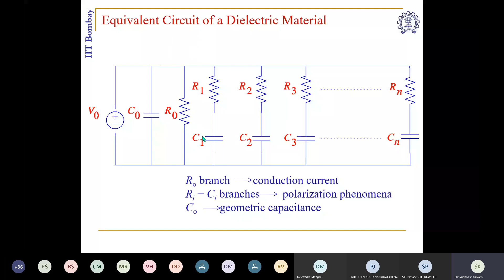Whereas this R0 is the final element. When we apply the DC voltage, eventually all the capacitances you see in this circuit will get charged, and then all those will become open circuited from the electric circuit point of view. The only element that will remain in this circuit will be R0. So V0 upon R0 is the final steady state leakage current that you generally measure. Whereas C0 is the geometric capacitance. That means if it is like a parallel plate capacitor, for example, C0 is simply epsilon 0 into area by the gap. It is only the geometric capacitance because the insulation inside that capacitance is represented by all these R1, C1, R2, C2, like that, R_i and C_i. So that is what represents the insulation, and that's why you have to take only C0 there, pure geometric capacitance.